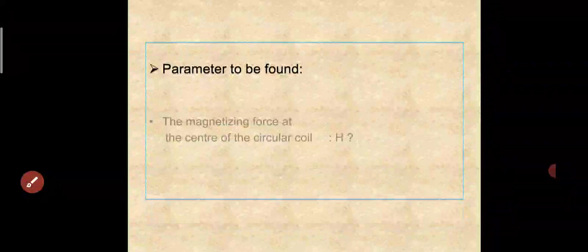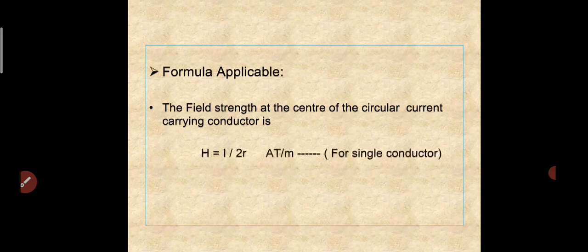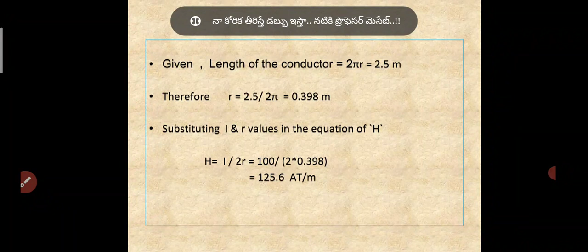See the given data: the circumference of the circular coil, the length of the conductor, is 2.5 meters, and the current through the conductor I is 100 amperes. So find the magnetizing force H. The applicable formula is H is equal to I by 2R ampere turns per meter for a single conductor. The length of the conductor is 2 pi R, so R is equal to L by 2 pi, which is 0.398 meters. Substituting the values in the equation, H is equal to I by 2R, so 100 by 2 into 0.398 is equal to 125.6 ampere turns per meter.